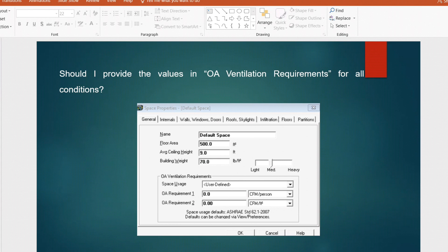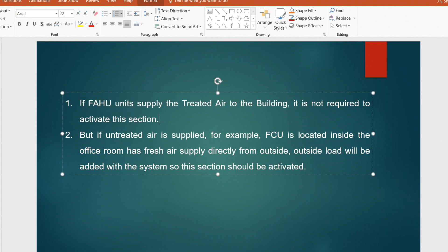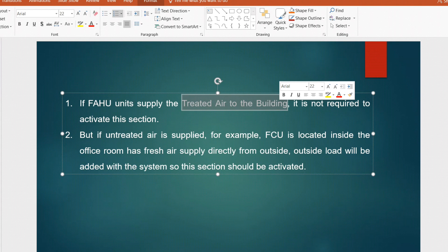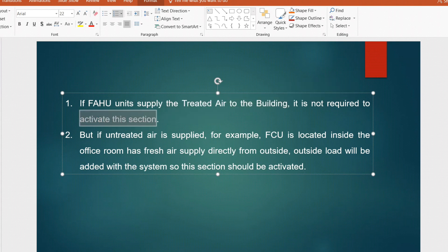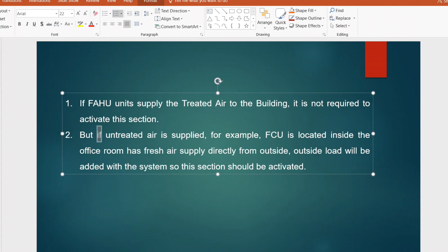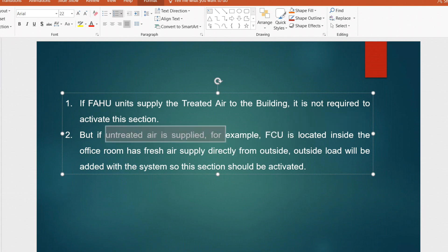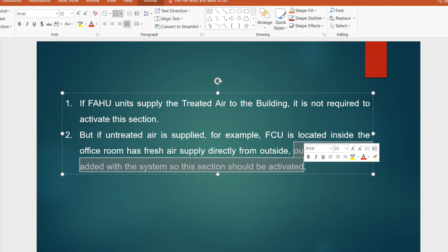When FAHU units — fresh air handling units — supply treated air to the building, it is not required to activate this outside air ventilation section. But if you don't have a FAHU and untreated air is supplied — for example you have fan coil units in the rooms and untreated air is supplied to those rooms — then we need to activate this section because the outside load will be added with the system. This section must be activated when doing the HAP cooling load calculation in that case.